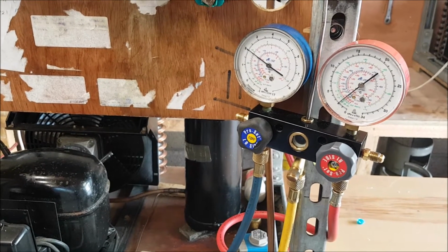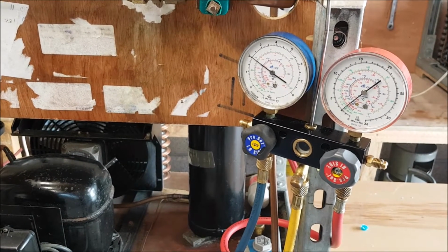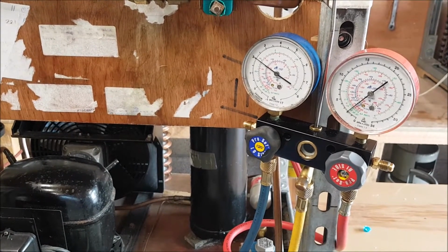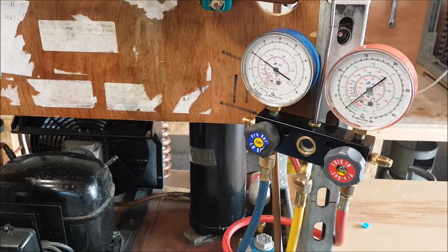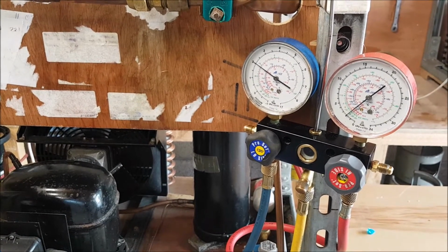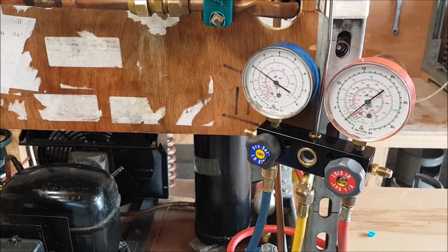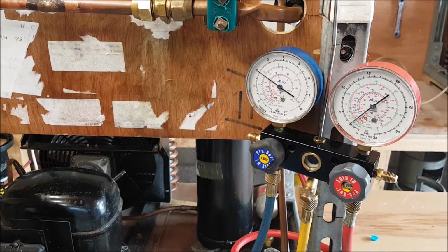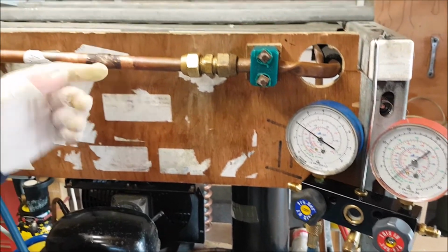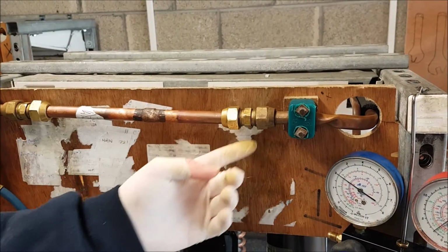You could hear the pressure switch clicking in. I'm as far as 2 bar pressure. 2 bar pressure is okay to start off with. And what we do then is we go around the system and check for potential signs of leak. Again, we can do a separate video on how to do leak testing, but at this point we are checking our braze joints, and we're using our fingers to see if there's any signs of oil.